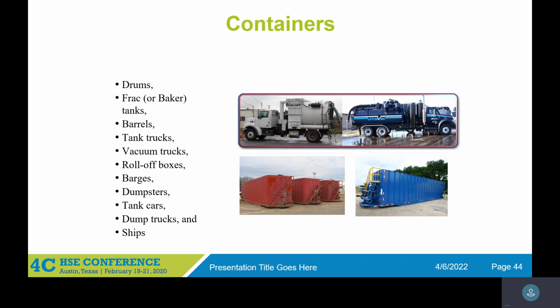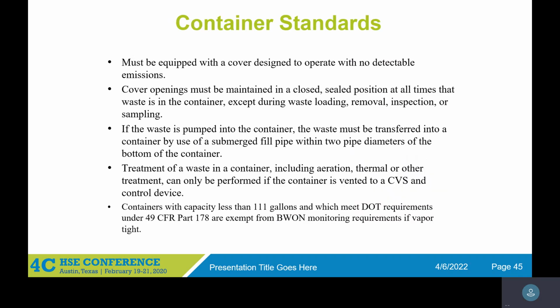So, like I said, these are the physical controls. The containment standards, all you have to do is submerged filling. While you're pumping, you have to do submerged filling. You just have to have a cover, and you have to route it to a closed vent system and control device if you're doing treatment in those. But if not, it's just having a cover. And if you are filling it, it's submerged fill.